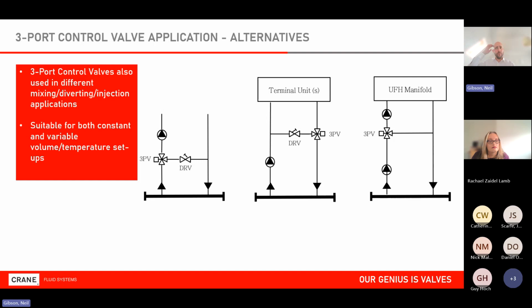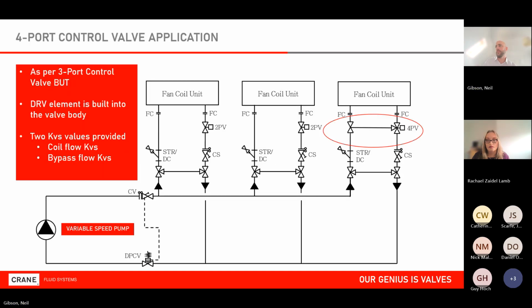We can also use 3-port valves in applications such as mixing and back at the pumps and injection circuits as well. So there's a place for these. It's not to say that we no longer need to use them in any capacity, but it is far more reduced. 4-port valves, a bit more specific, a bit more niche, are typically on fan coil units where we've got a 40mm pitch between flow and return. So does a 4-port valve, and we can fit it directly over a drip tray. Same application as a 3-port valve. We'd use that for minimum flow circulation and minimum flow in the pumps.